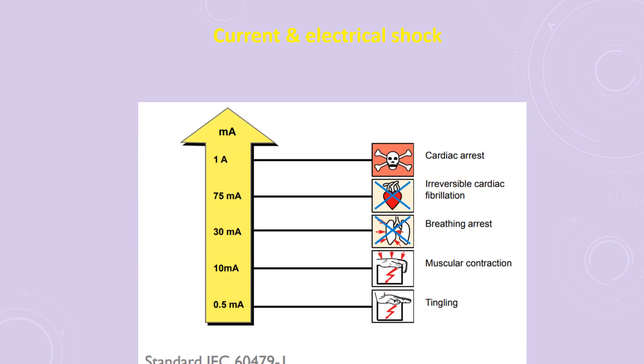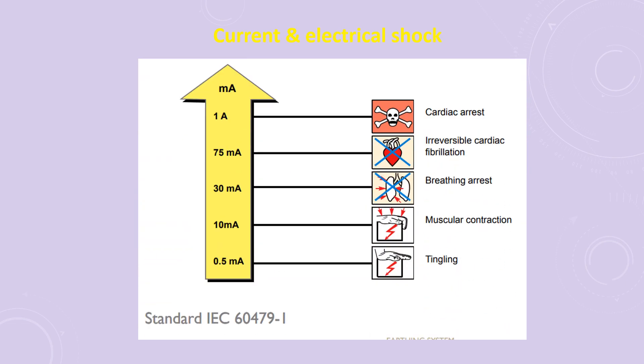Now let's see how much current flows and what will happen inside the body. At 0.5 milliampere, you will feel the sensation of current. At 10 milliampere, your muscles will contract. At 30 milliampere, breathing arrest occurs. And at 1 ampere, you will get cardiac arrest — your heart will fail. This is what happens when current flows inside the body.